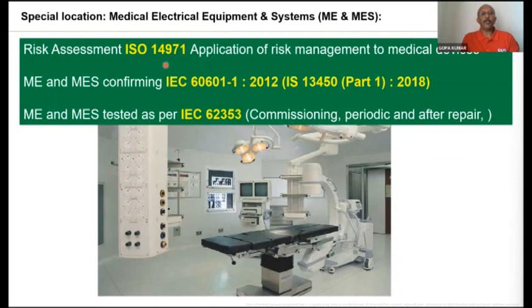So the risk assessment is mandatory. I'm telling you, these are actually followed internationally very well. And all the medical electrical equipment and medical electrical system must conform to the IEC standard 60601. Actually, there is an equivalent Indian standard, IS 13450 part 1 2018.